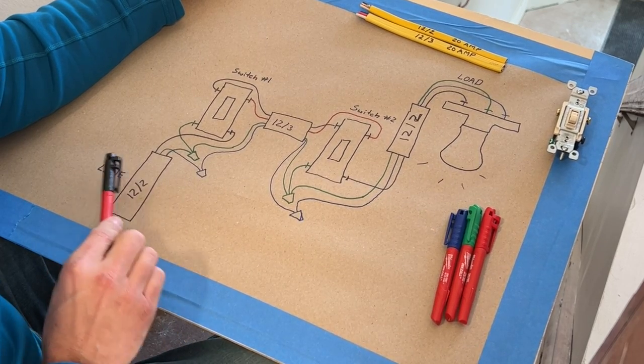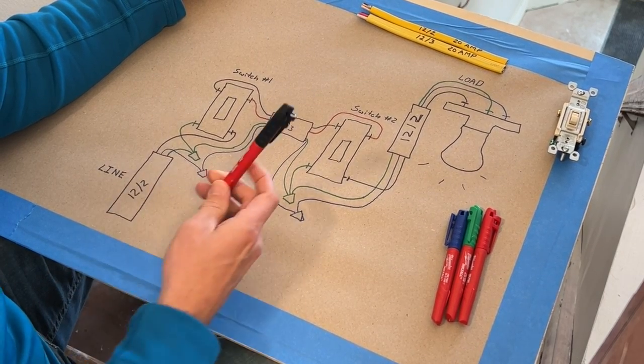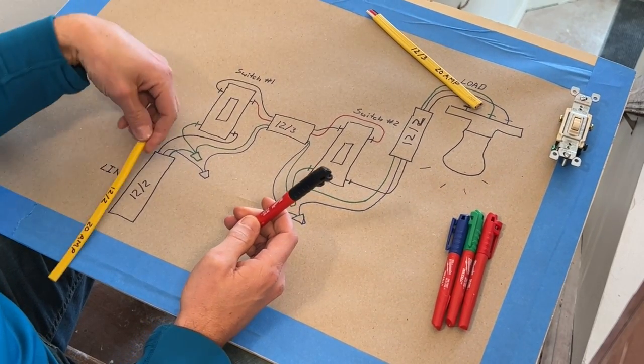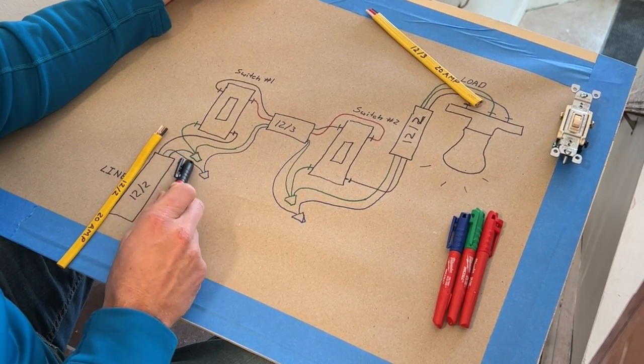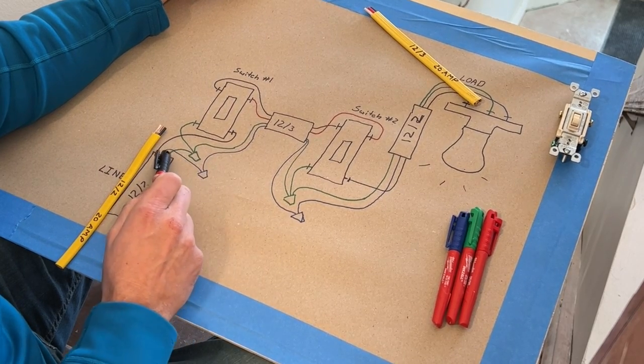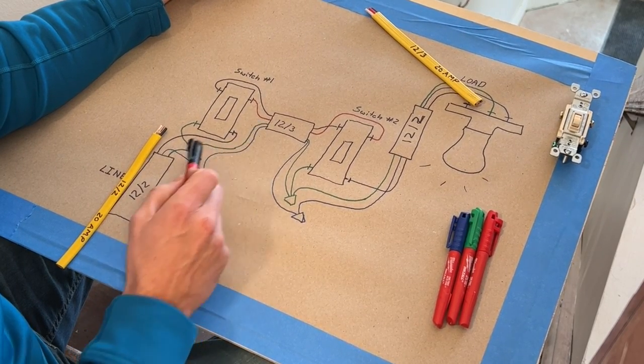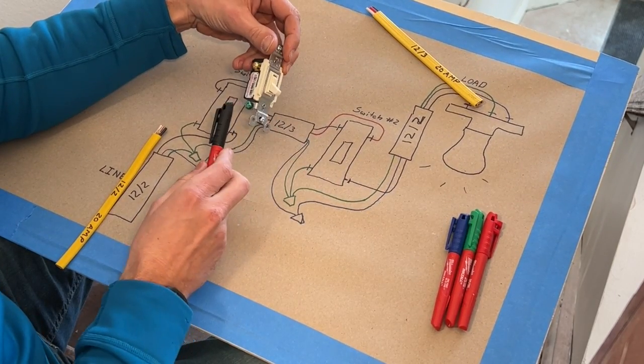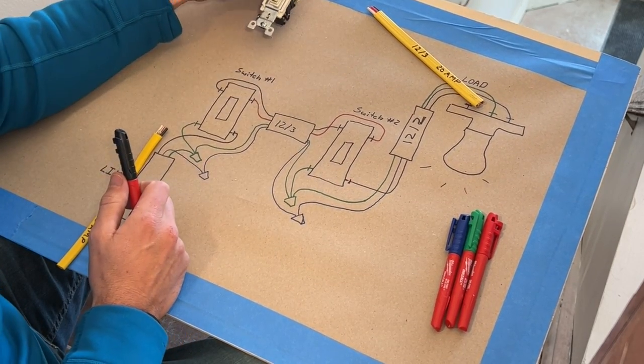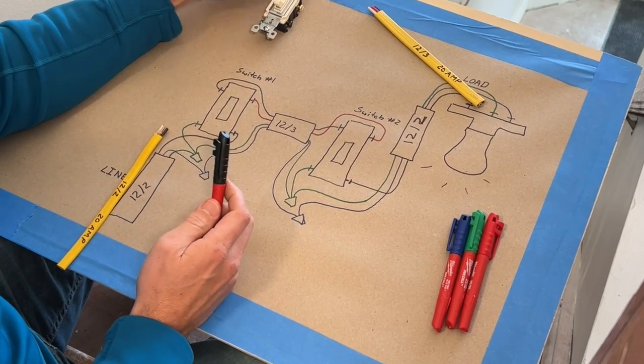We'll start off here on the line side. We'd have a 12-2 wire coming in. We would be passing our neutral through and also passing our ground through, but taking a pigtail out to our switch. So we'd be pigtailing to ground the switch itself.